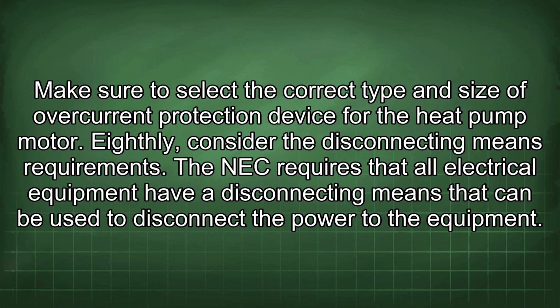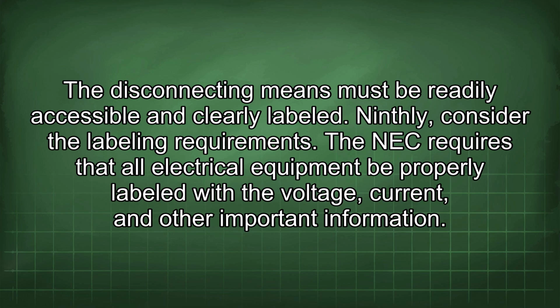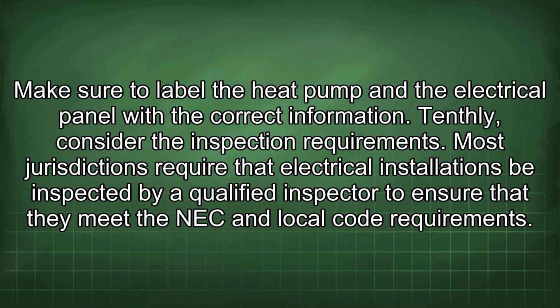8th, consider the disconnecting means requirements. The NEC requires that all electrical equipment have a disconnecting means that can be used to disconnect the power to the equipment. The disconnecting means must be readily accessible and clearly labeled. 9th, consider the labeling requirements. The NEC requires that all electrical equipment be properly labeled with the voltage, current, and other important information. Make sure to label the heat pump and the electrical panel with the correct information.